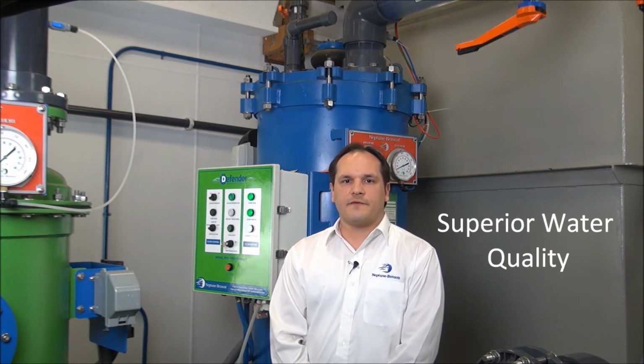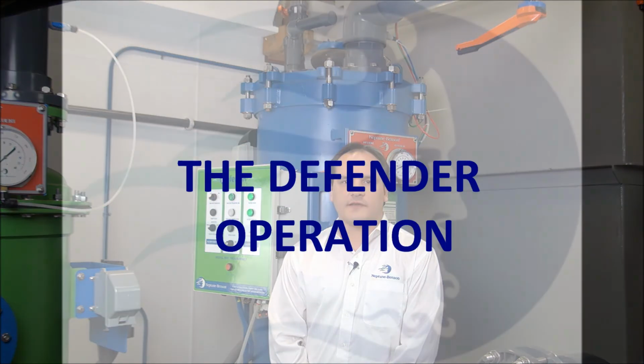The ability for the Defender filter to filter down to 1 micron on day 1 through the entire life cycle of the filter media. Whereas a sand filter will only filter down to approximately 30 microns when the bed is clean and might get down to 15 to 20 microns when the filter bed is dirty and has the ability to collect smaller particulate.